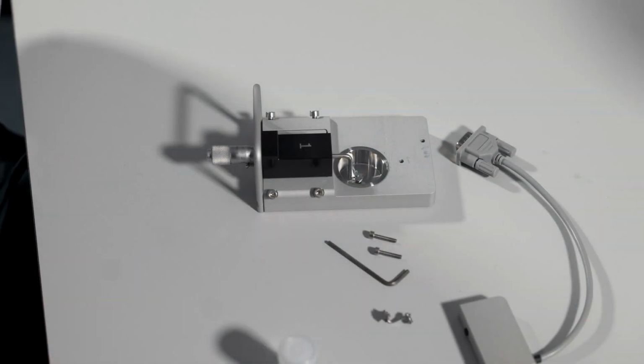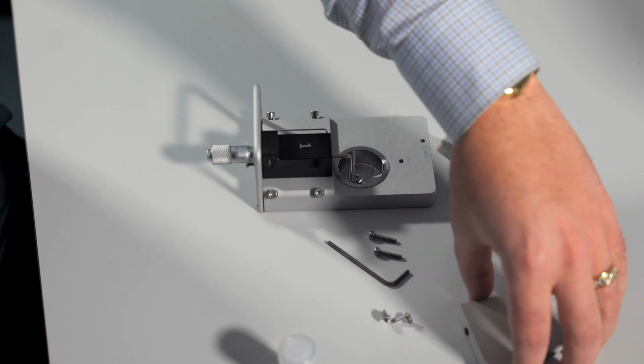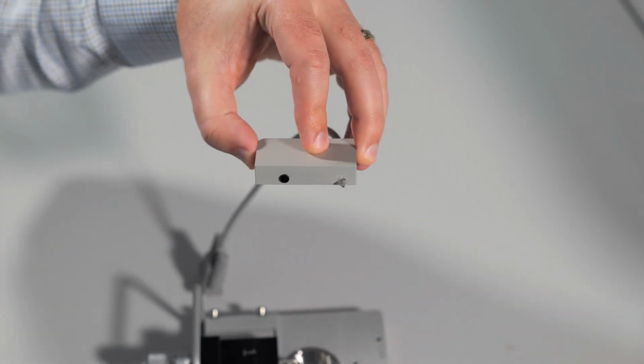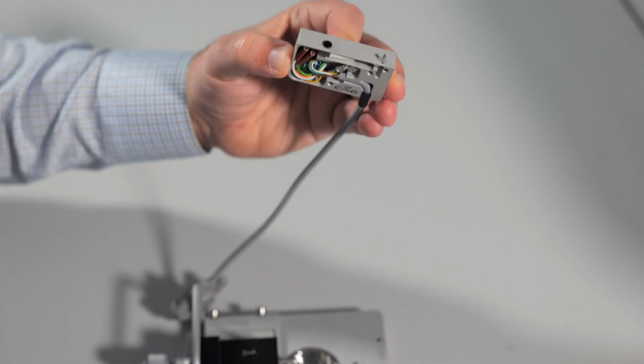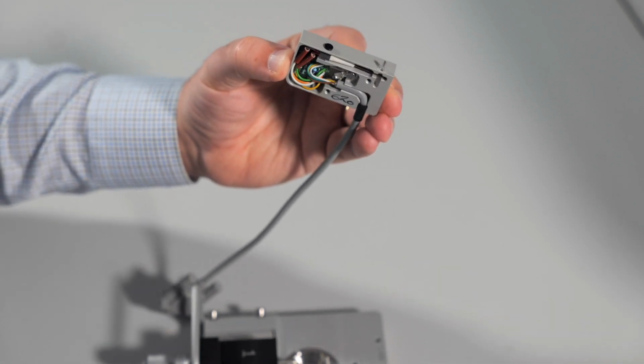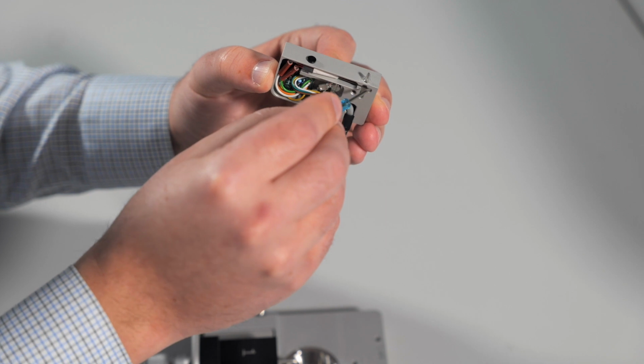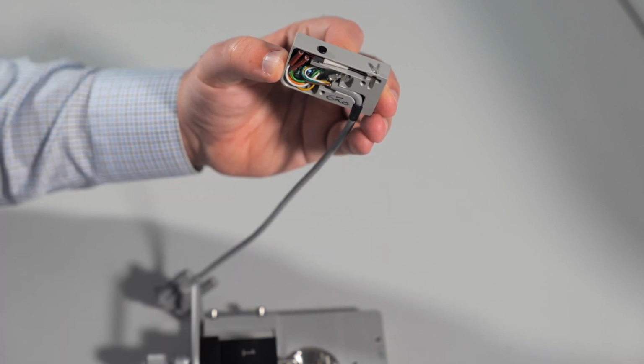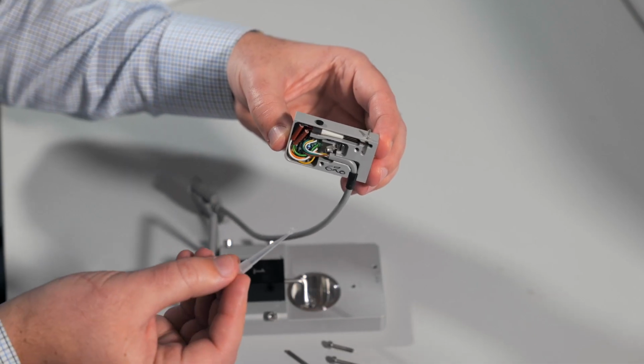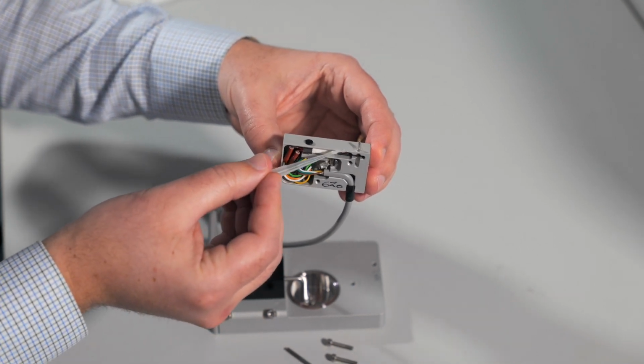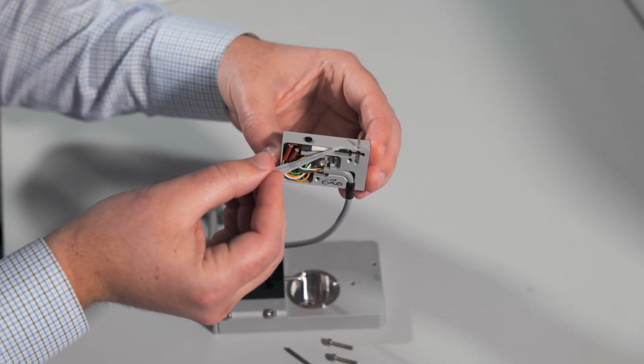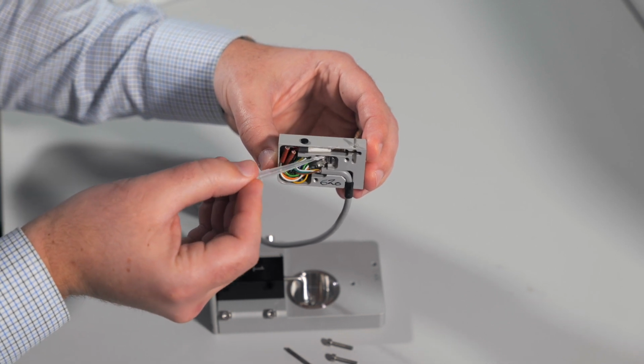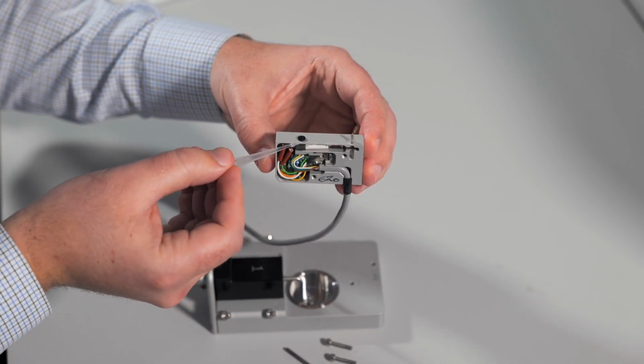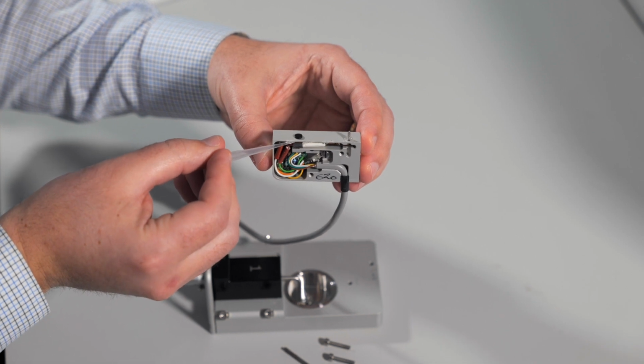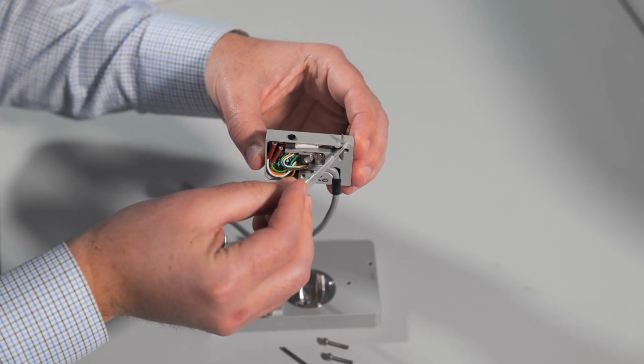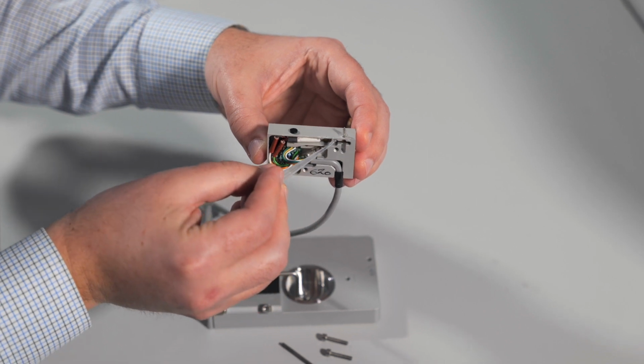To prepare the transducer for the chamber, you want to make sure that it's properly greased. You can see here that this transducer has been greased already, but if it is not, you will take either a pipette tip or a 1 ml syringe and apply some of the clear silicone-based grease around that pinhole. It is also a good idea to add grease along the front edge of the transducer. This will protect against any liquid entering the transducer housing. You can take your pipette tip with grease and apply it along this edge.